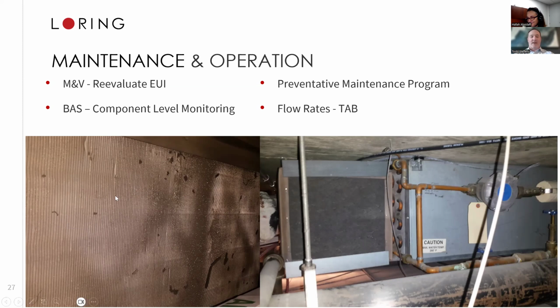And those dark areas are where dust actually circumvented the original filter frame and attached itself to the cooling coil. Cooling coils get wet, and if wet coils with dust on them then dry out later, now it's caked-on dust on these cooling coils. And it just reduces the heat transfer efficiency.